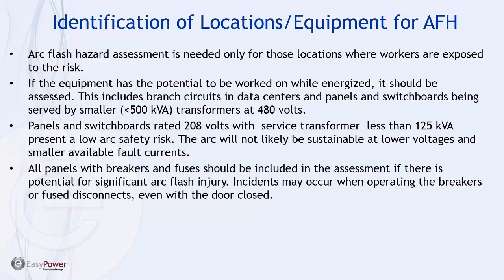The arc flash hazard assessment is primarily for those locations where workers are exposed to the risk of arc flash. That means if the equipment has the potential to be worked on while energized, inspected, or maintained in any way where bare conductors are opened up to human exposure, that's potentially an arc flash hazard that needs to be identified and at the very least labeled. This includes even branch circuits, and in older facilities this ends up being a problem specifically at 480 volts and below at remote panels when distributed discrete protective devices haven't been properly installed or designed in the system.